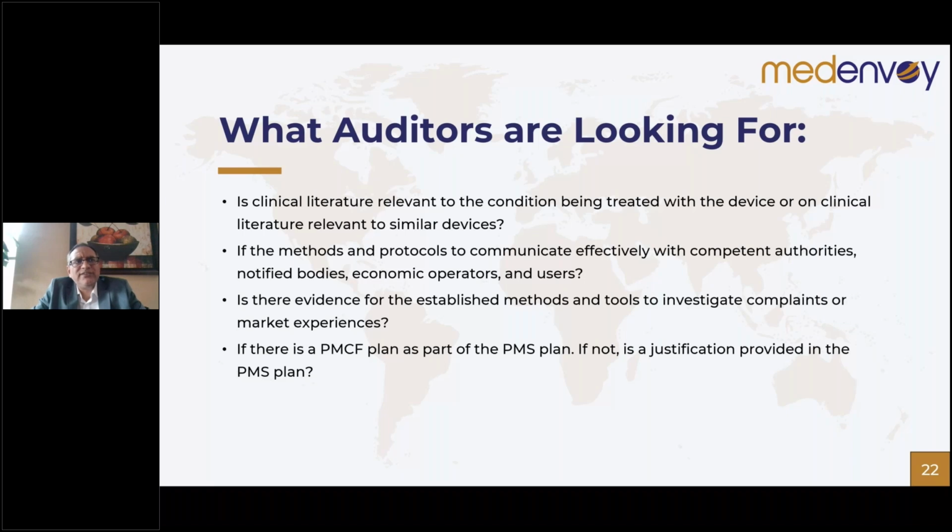When you investigate a little more, you realize your partners, your distributors, your importers, are not reporting back the issues to manufacturers. In their opinion, they are handling and managing it without reporting it back to the manufacturer. So it's important that you communicate with the economic operators downstream, that whether they are serious or non-serious, or whether they are handling it or not, it must be reported back.